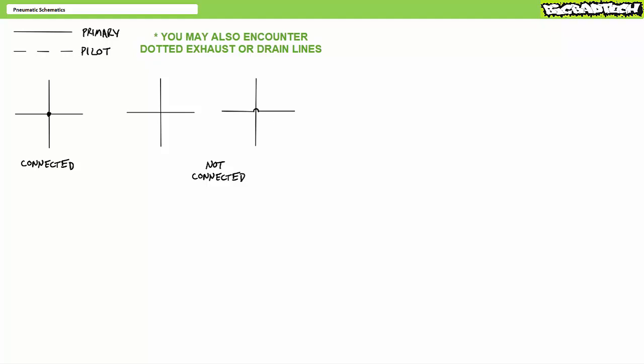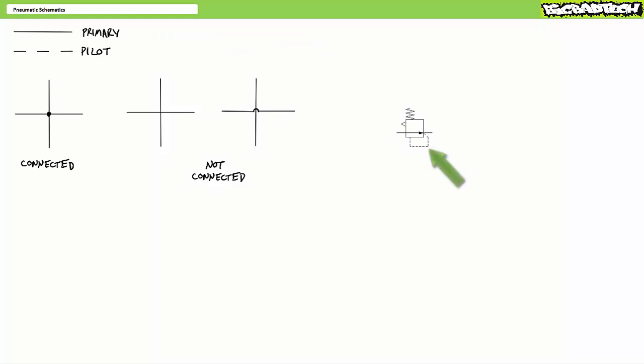In contrast, pilot lines, i.e. the sensory lines and passages that transmit low pressure, low flow rate, air-based control signals, are represented schematically as dashed lines. You'll often see pilot lines internal to another device's schematic symbol indicating which port is being monitored by the pilot passage.